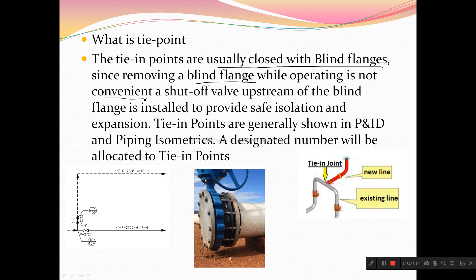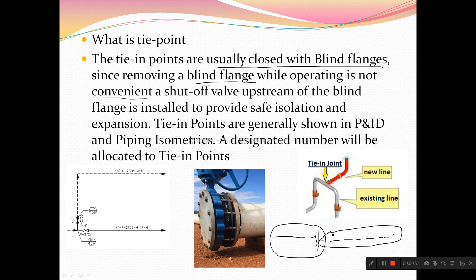It means when I have a main line, if I have a connected flange and a blind flange, from this point my new line is getting started — this is my existing part. A new line gets connected from this point. If I remove the blind flange and connect a new line while flow is on, when I open the blind flange all the flow will come outside.